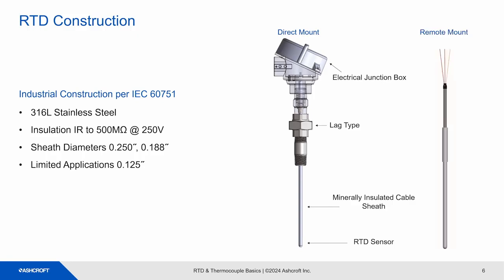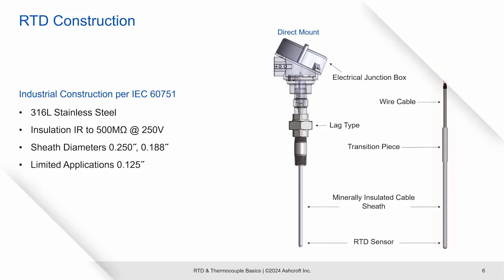There are also remote mount probe styles. The RTD sensor is at the tip of the probe. They use MI cables. They have a transition piece to connect the MI cable wires to the extension wire cable. The wire cable can come in a variety of wire insulation types and can have flex armor for additional protection.